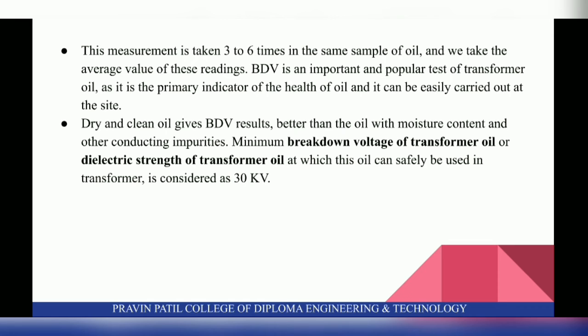Dry and clean oil gives better BDV results than oil with moisture content and other conducting impurities. The minimum breakdown voltage of transformer oil, or dielectric strength of transformer oil, at which this oil can safely be used in the transformer is considered as 30 kV.